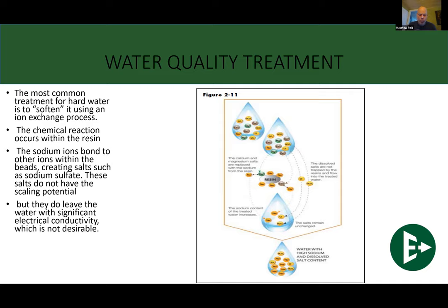Now you start to erode things from the outside in. If the water is able to conduct electricity, it's going to. And this is what I mean by that. It's not just with regards to grounding out those pipes. Well, do that as much as you can, but it'll pick up that electricity and start to erode all the systems from the outside in by things as simple as static electricity in the air. You can have problems with that. You have problems on your connections. Any bimetal connections, if you're not using a really top quality dielectric union, it'll absolutely fail in that area.